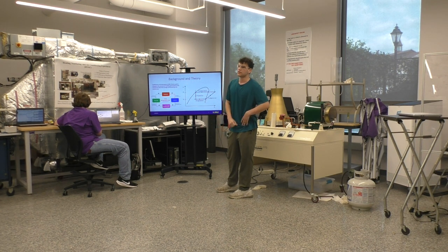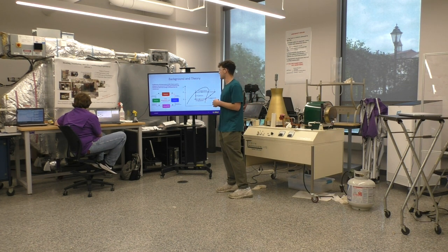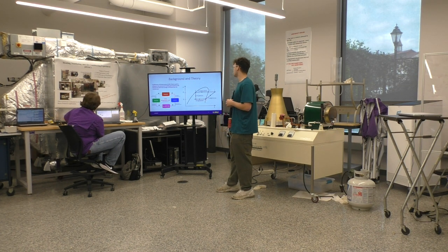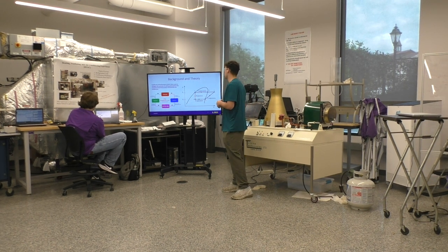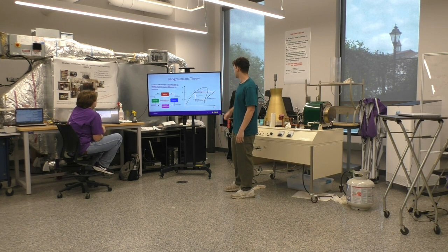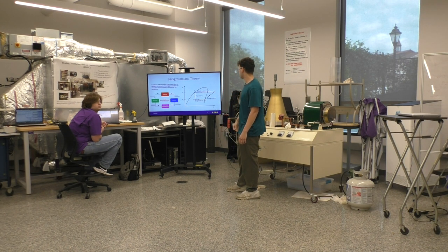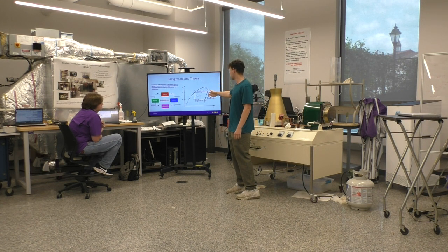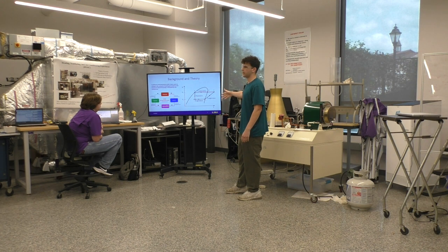And to give us a metric of how this works, the main thing is the coefficient of performance. This is a ratio used to compare the amount of cooling generated to the amount of electrical energy consumed by the compressor. And to the right, you can see the pressure versus enthalpy diagram for the different states, where we have the energy input at the compressor from 1 to 2, and then we have energy output at the condenser from 2 to 3, and then from 3 to 4 where the liquid is expanded, and then 4 to 1 where it evaporates and starts over.